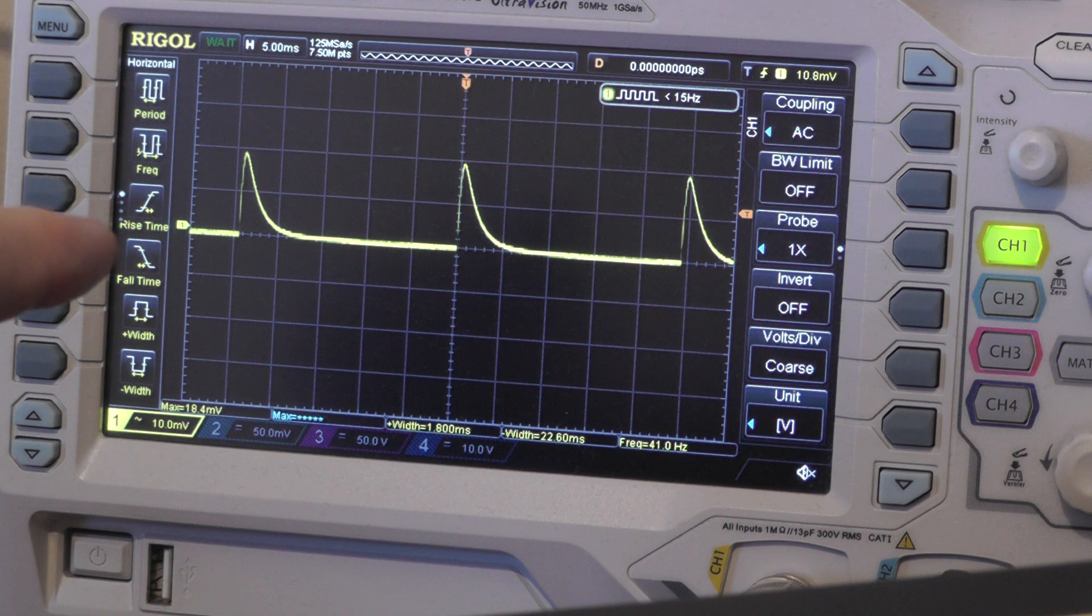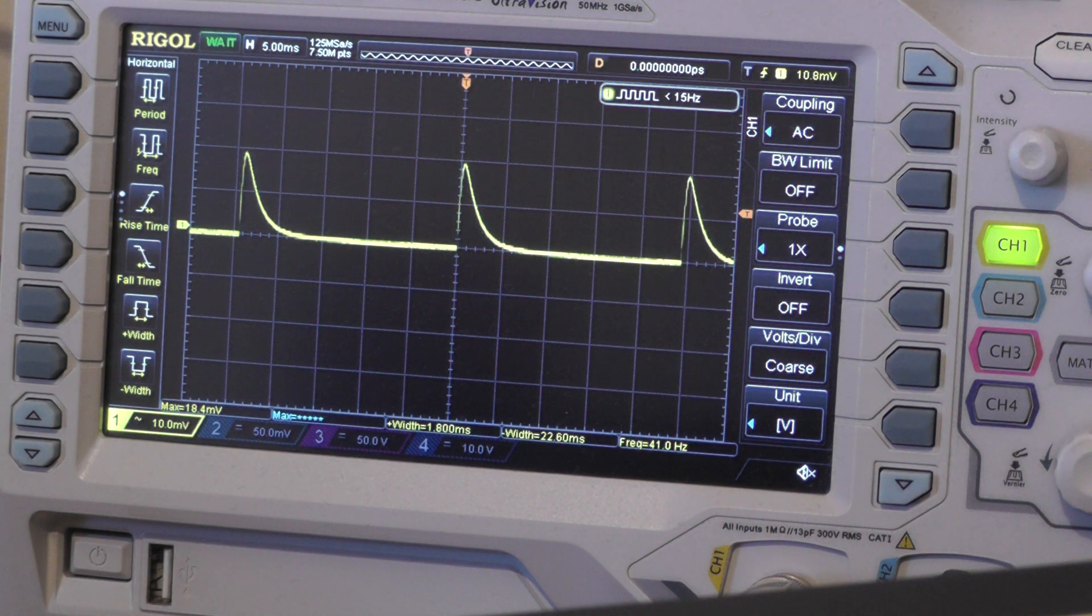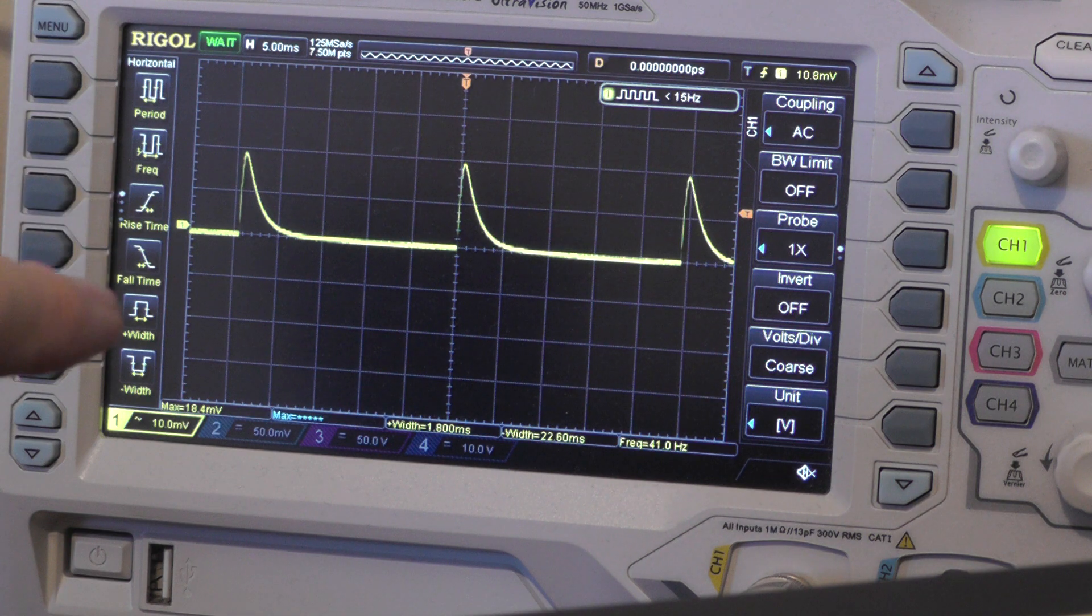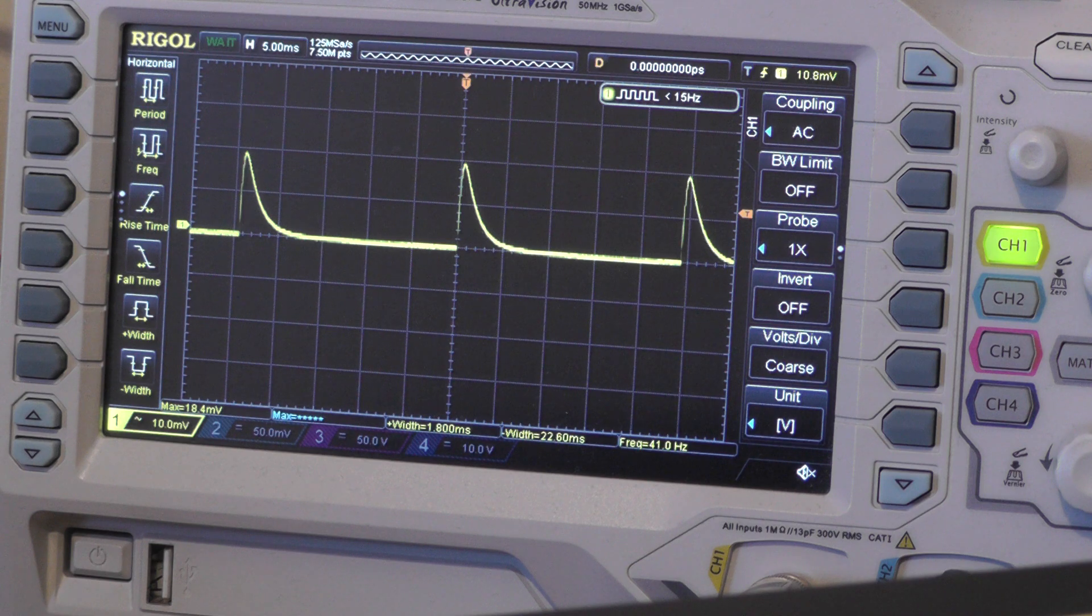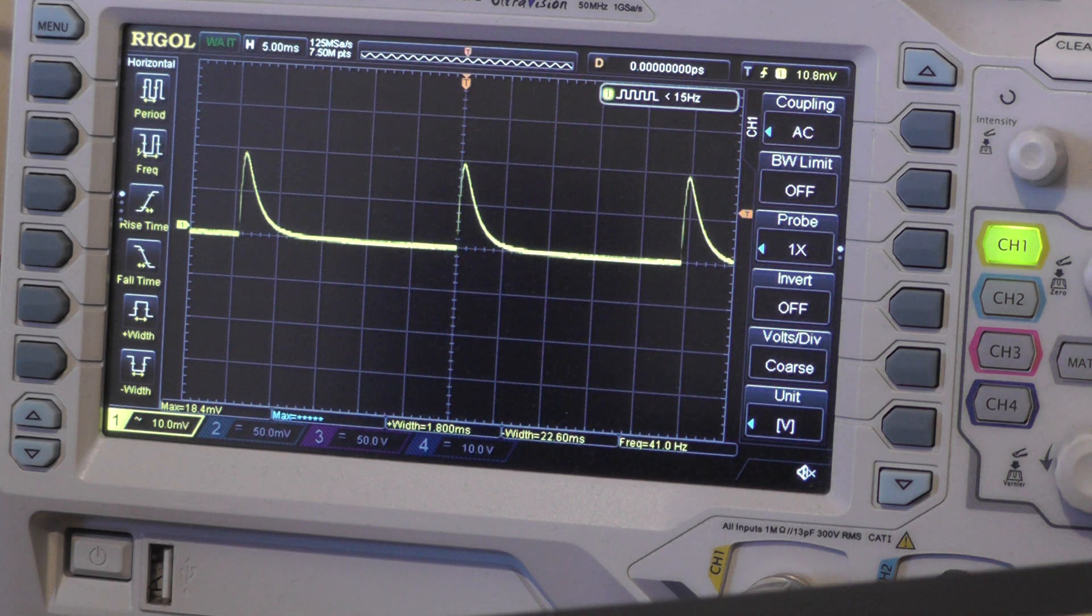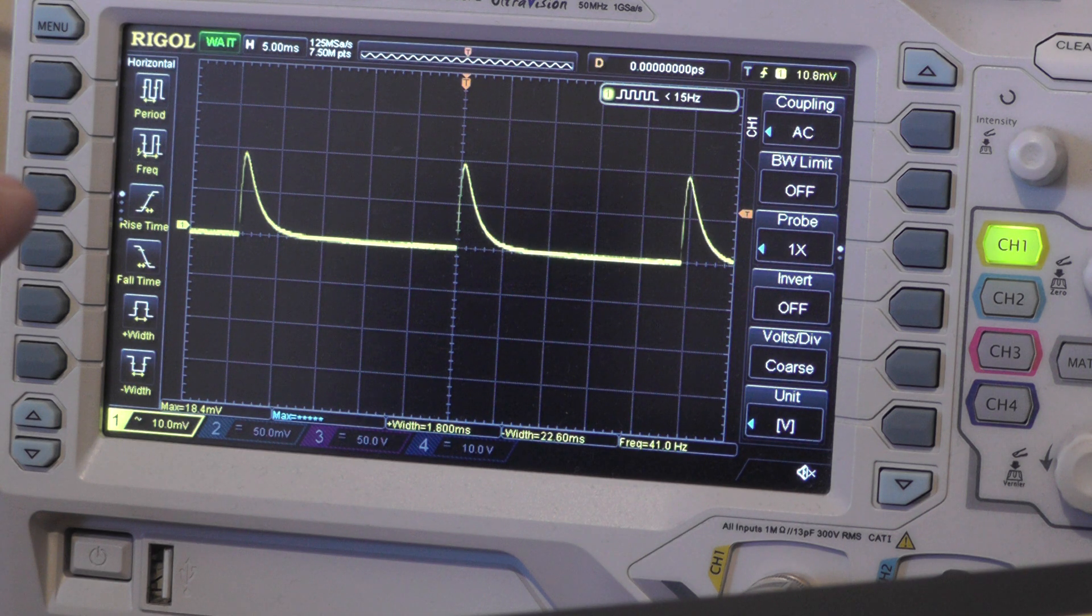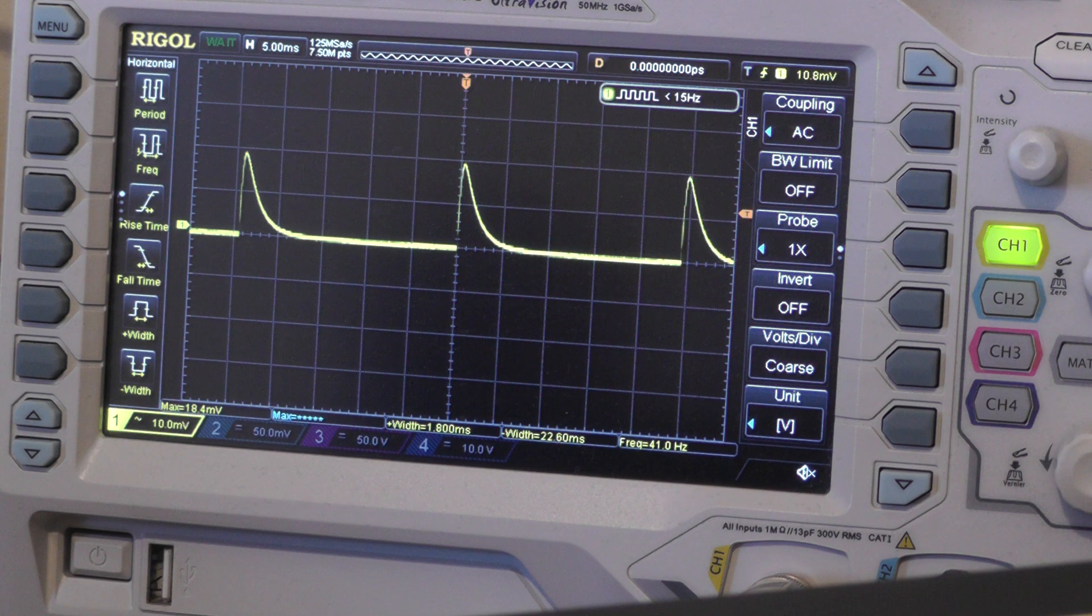So here's the output of the energy sensor on the oscilloscope and we can see that we're measuring 20 millivolts out from ground to peak. We can take that figure and the original calibration figure of 134.3 volts per Joule and actually work out what the output power of the laser is. I actually put together a handy little JavaScript calculator to do that so let's go and take a look at that just now.